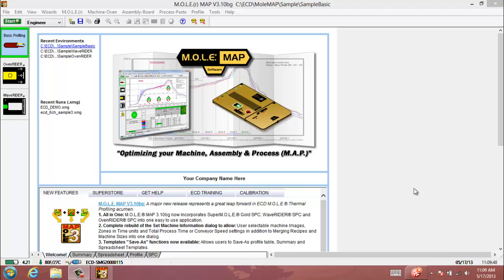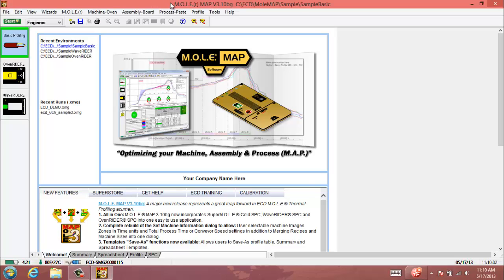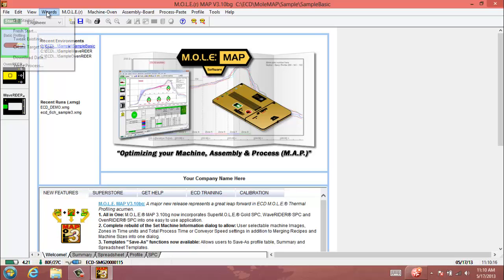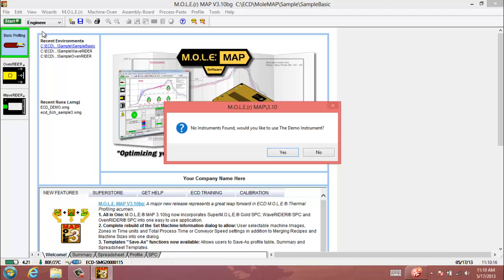Today we're going to take a look at the Fresh Start Wizard in Map Software, which is a great process to go through if you just received a new profiler from ECD and want to get it programmed and set up to profile with. To begin, go ahead and launch your map software, connect your mole to the PC, and we'll start by selecting the Wizards drop-down menu at the top. In this video, we're going to go for the Fresh Start Wizard.